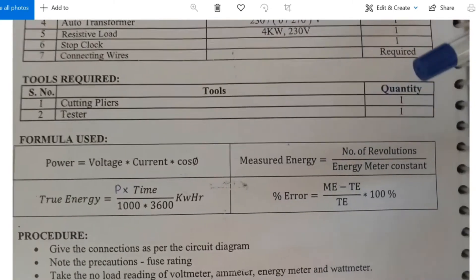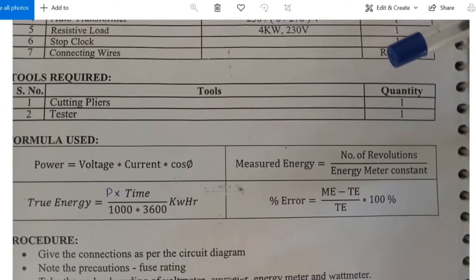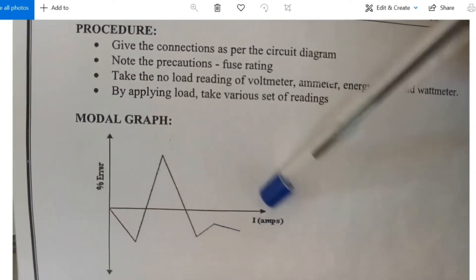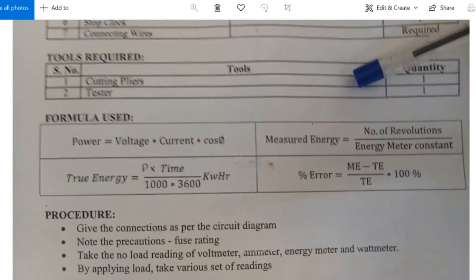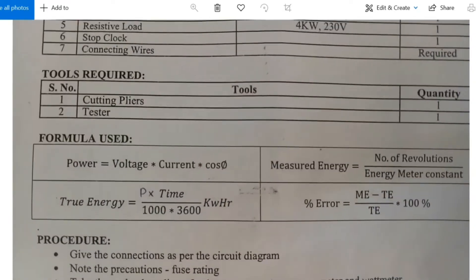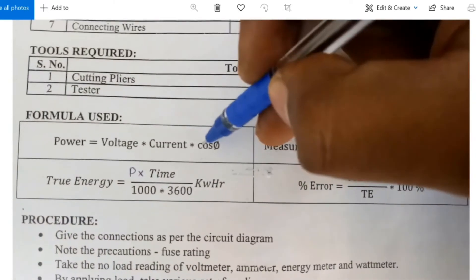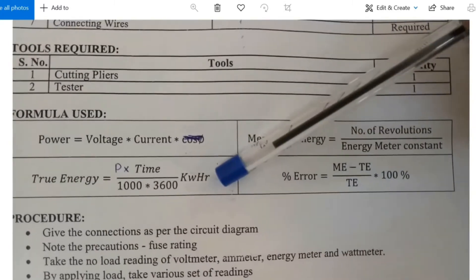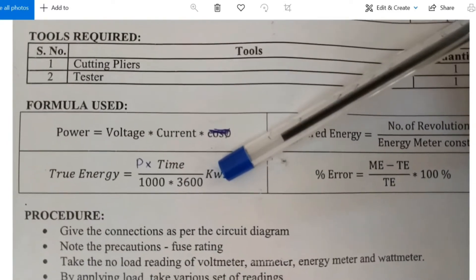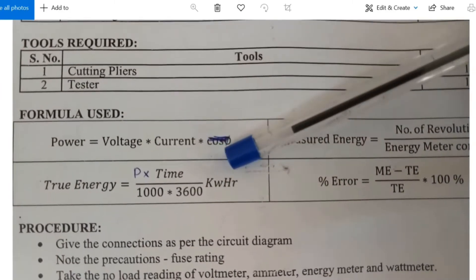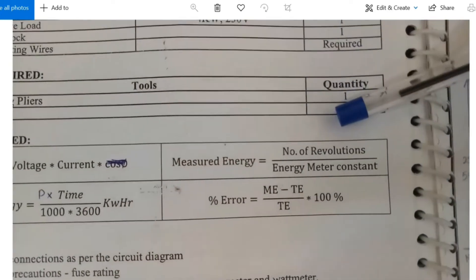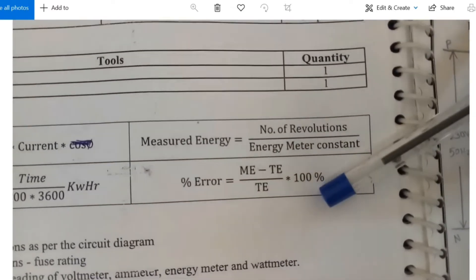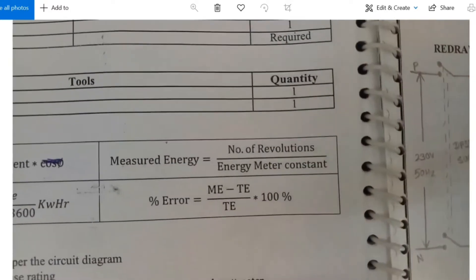The formulae required for calculations: Power equals voltage into current. True energy equals P into time divided by 1000 into 3600, giving kilowatt-hours. Measured energy equals number of revolutions in the energy meter divided by the energy meter constant. Percentage error is calculated as measured energy minus true energy, divided by true energy, into 100.